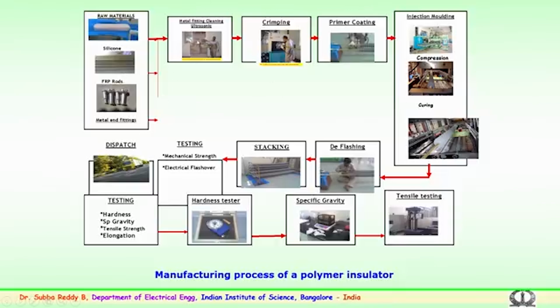Then the metal fittings are fixed at the ends of the fiberglass rod, so proper crimping has to be carried out. After the crimping of the metal end fittings on the fiberglass rod, a primer is coated on the fiberglass rod. Further, with the help of an injection molding machine, suitably under compression and curing, the polymer material is molded with the proper die set. It is later cured. After the curing, deflashing of the insulator is done, where the extra material present after the curing or compression is removed, and it is neatly stacked.